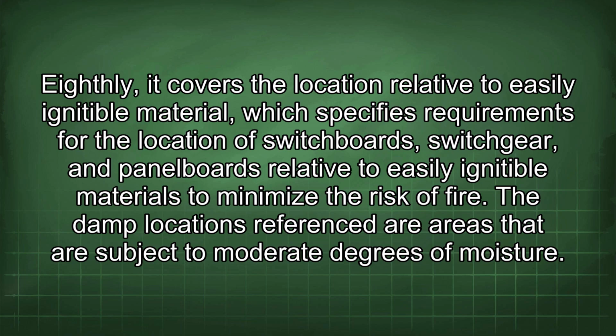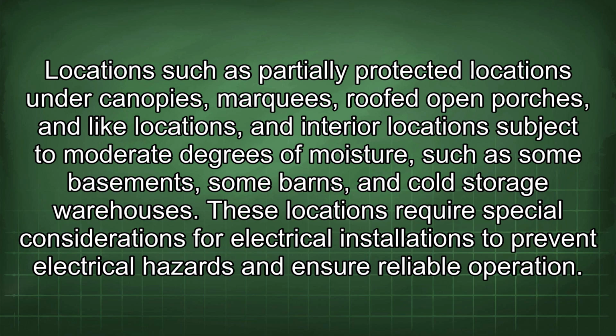The damp locations referenced are areas that are subject to moderate degrees of moisture. Locations such as partially protected locations under canopies, marquees, roofed open porches, and like locations, and interior locations subject to moderate degrees of moisture such as some basements, some barns, and cold storage warehouses. These locations require special considerations for electrical installations to prevent electrical hazards and ensure reliable operation.